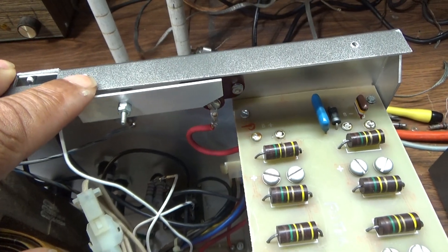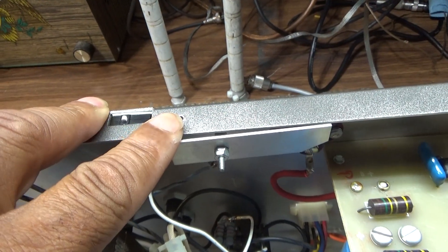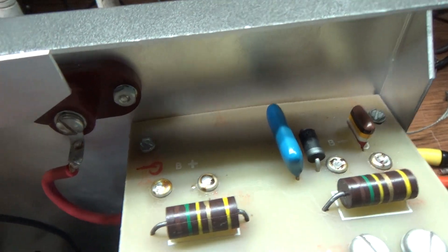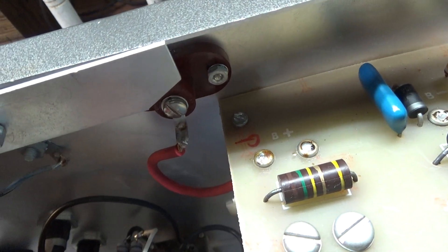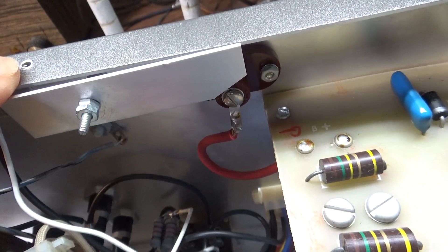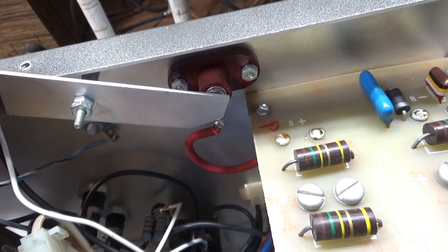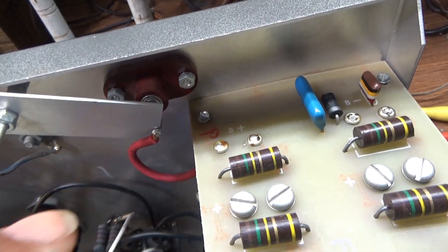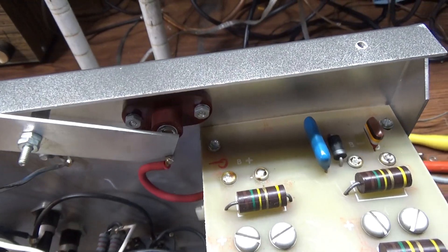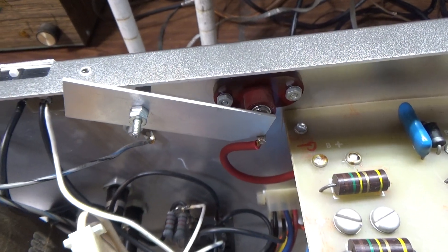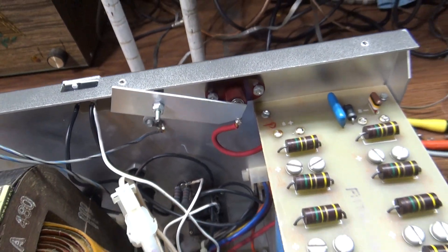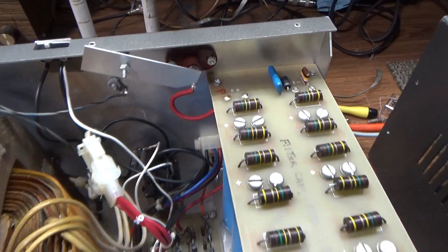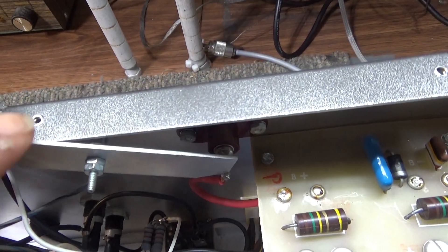When you put the cover on, the cover pushes down on that and lifts that arm off the high voltage. When you take the cover off, this just falls down by gravity and connects to the high voltage there, and it shorts out the high voltage. So if we try to power this amp up with the cover off, that would short out the high voltage.